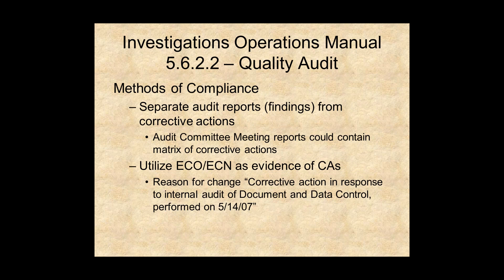Something to remember here is I'm not dictating that you do this. From my experience, this is a method of compliance that has withstood scrutiny during FDA inspections and reviews. What you want to do is separate the audit reports — the findings themselves — from the corrective actions. A couple of ways of doing this: some facilities have audit committee meetings where they go through each subsystem that has been audited during the year and discuss how many findings there are and their closure status. Such a document may not need to list the specific findings, but merely finding numbers.